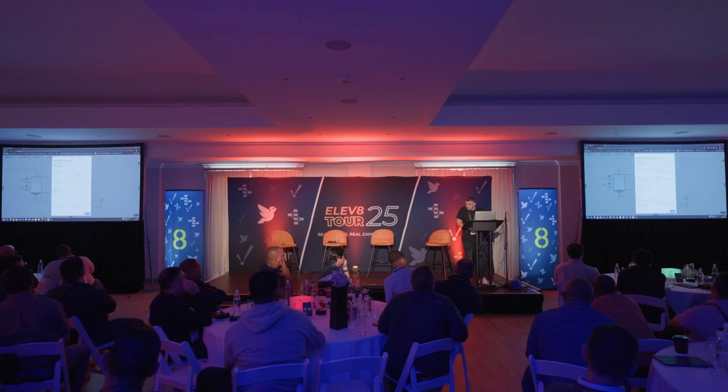I selected email. So how this will work is you will basically subscribe to an event. So what I'm going to do is on this valve, I'm going to subscribe to an alarm event, and I want to know when the state of the alarm has changed. Meaning when the alarm goes through, I want to get an email. And I only want to do that for the next, what's the date? Let's say 24 hours. Okay, this is maybe useful when technicians just fix the valve. They just want to know for the next 24 hours, is the valve actually still working? Just to have some visibility.